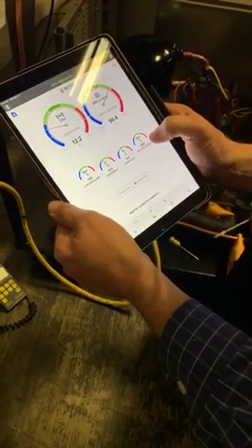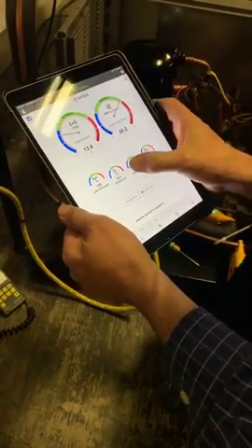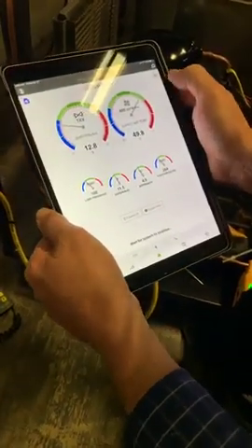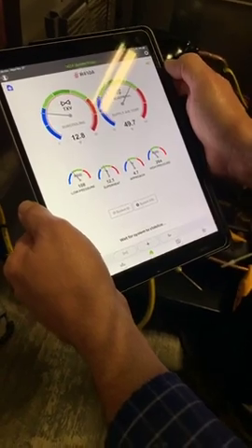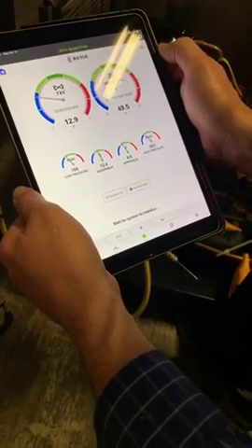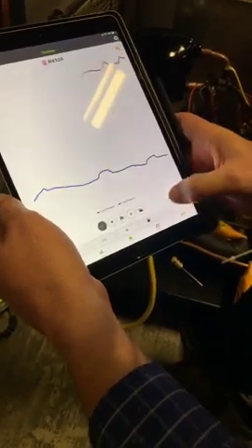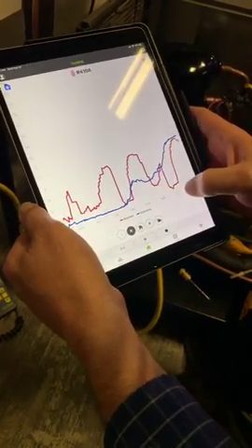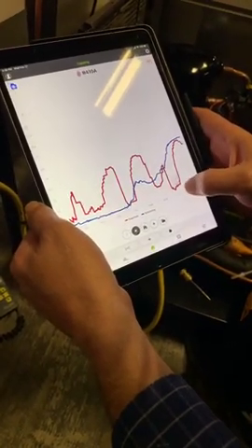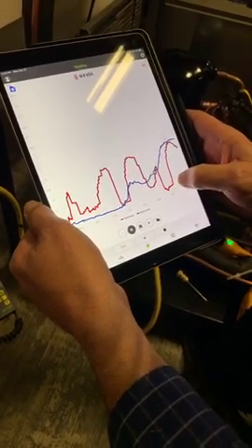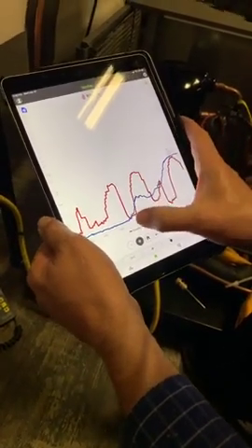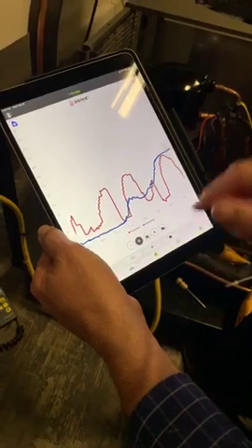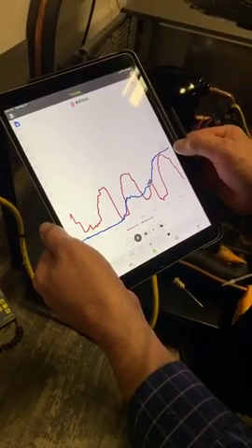And now you can see our high pressure is coming up closer into range. Approach is looking good, superheat's looking good, and low pressure's looking good. Temperature split's looking good. That's dropping a little bit, meaning we're cooling a little bit better. And the only thing we are a little bit off on is the subcooling target. If we scroll back and look at our trend lines here, you can see every time I add refrigerant, that drop in superheat. You want to make sure you're always maintaining some superheat. I'm getting a little bit low here at 1.4, but we always want to have some superheat. And you can see each time subcooling was down at 0.6, 4.5, now it's up to 13, and our target's 18, but you can still see it's increasing.